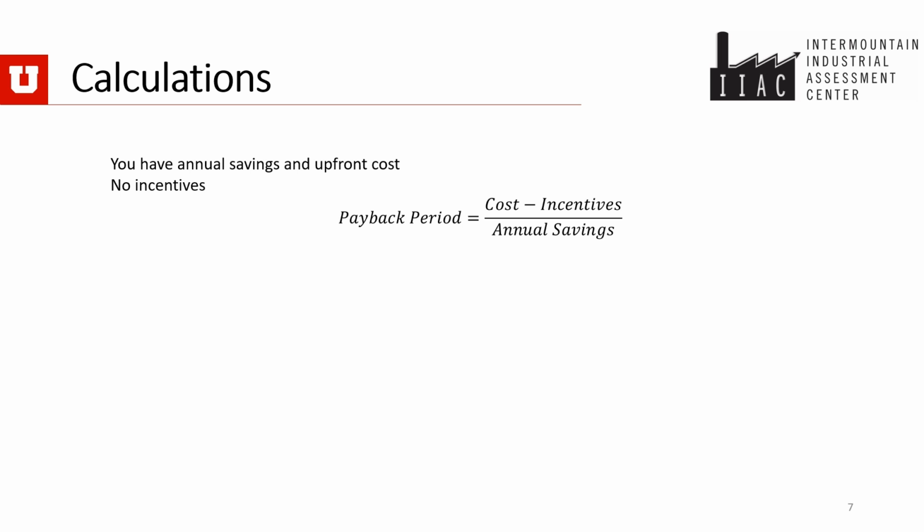Typically, since power factor is cheap and easy to manage, this will be under 1 year. If it's not under 1 year, it should be under 2. But the IAC policy is as long as it's under 5 years of payback, then it's worth recommending. I've never seen a power factor AR get turned down for having too high of a payback period. So get this number and you can move on to your write-up now that all your calculations are done.